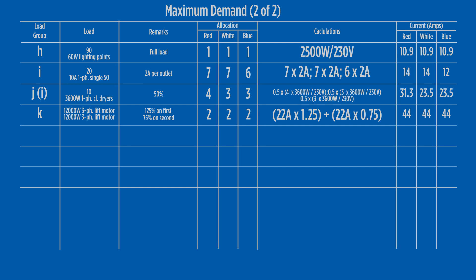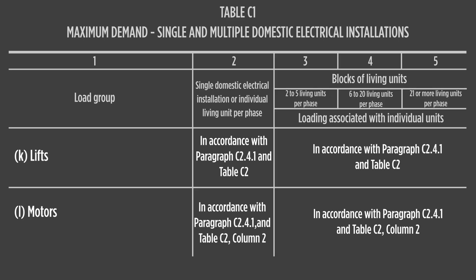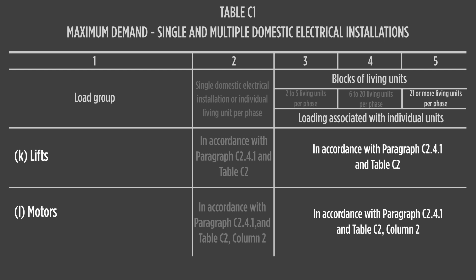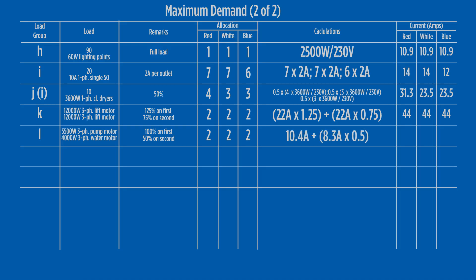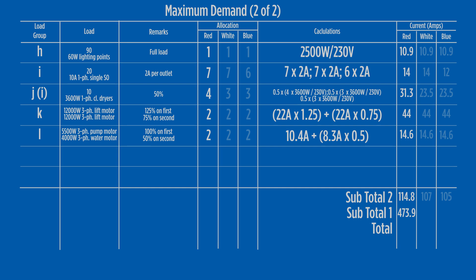The final calculation is for two three-phase motors, one at 5.5 kilowatts and the other at 4 kilowatts. For load allocation, group L in Table C1 directs us to Table C2 again. In column 2 of Table C2, full load current is applied for the first motor and 50% of full load current for the remainder. The calculation gives us 14.6 amps, with the total loading for the communal services being 114.8 amps. All that remains is to add the unit and communal service loadings together: 473.9 plus 114.8 equals 588.7 amps for the estimated maximum demand.